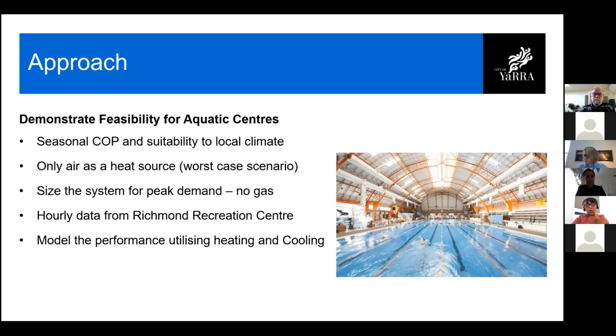So when we go into the project and actually electrify our aquatic center, we will probably use heat recovery from pool hall air exhaust, maybe tap into wastewater mains if we can. We will try to use as many heat sources as possible to improve the efficiency. But for the purposes of the study, we wanted to do a worst case scenario modeling to show that, with just cold ambient air in the winter, we will still have enough energy to cover our peak demand, which is also in winter. We sized the system for peak demand, so no gas backup at all.